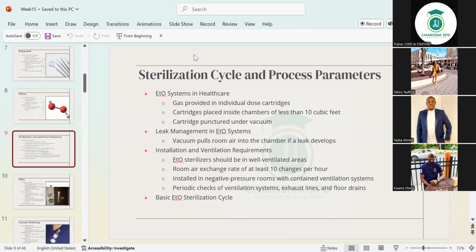Vacuum pulls room air into the chamber if a leak develops. So look at it this way. Just as we said in the decon, the decontamination area always has a negative air pressure. That's the same thing that is happening here. So the air from there will not come out to harm you, but if there's a leak, the vacuum is going to pull room air into the chamber. So instead of the leak coming out and you getting exposed to the gas, it's going to stay within, because it's going to suck air from outside to go in. That's how leak management in these ETO systems works, if it works right. Any questions?